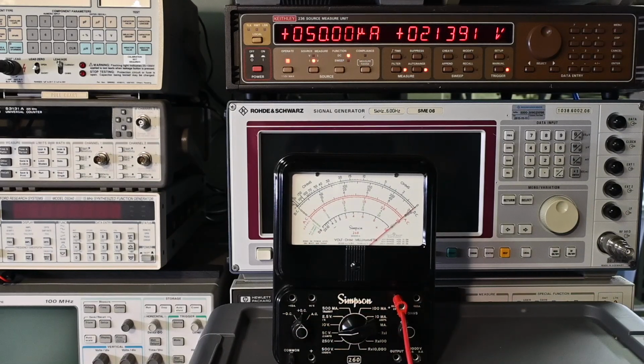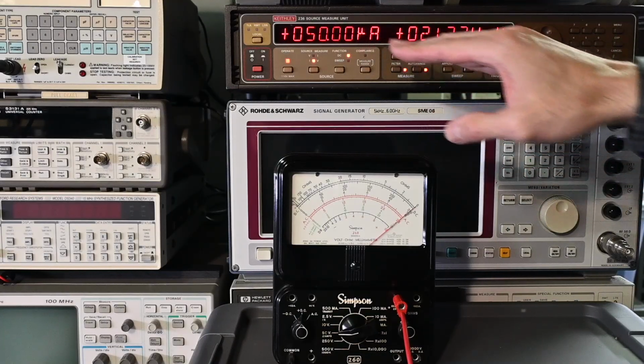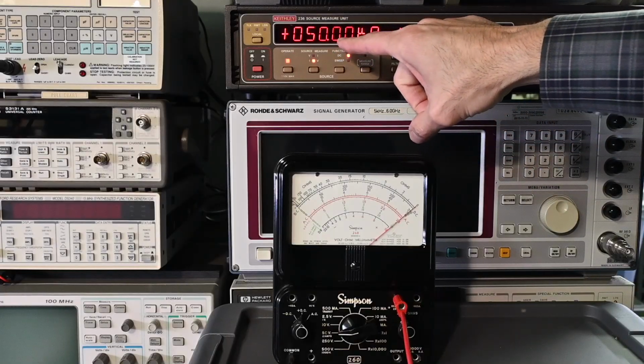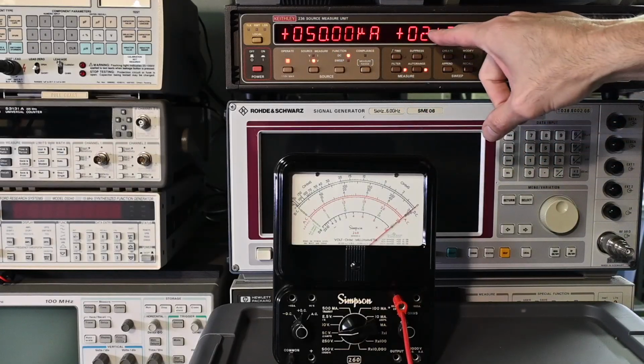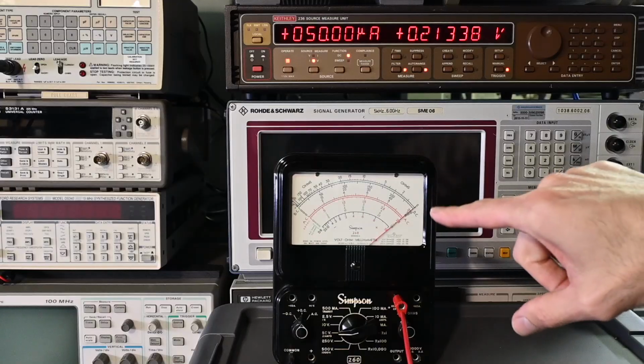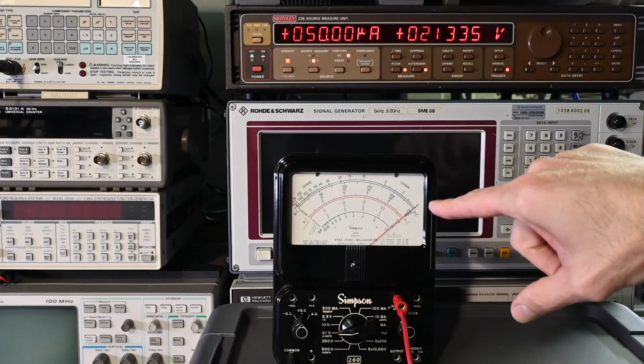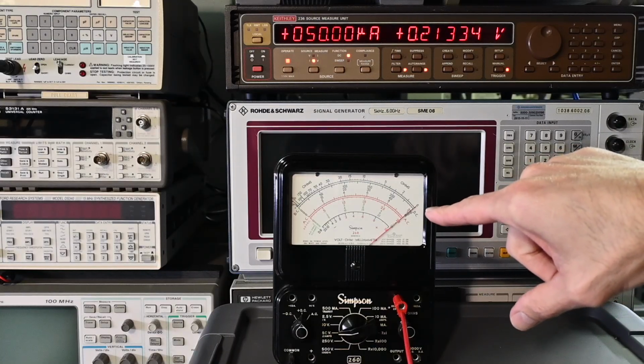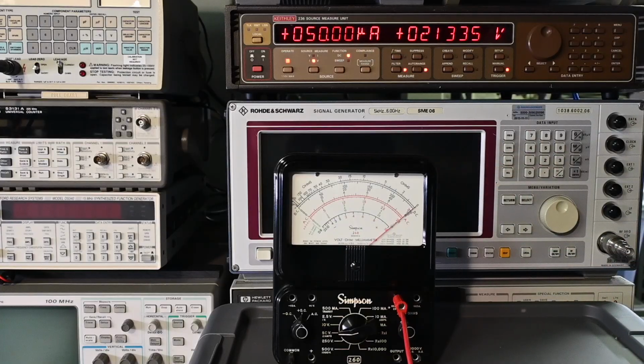All right, so I want to show you what not to do first when you're doing the second DC calibration, and that's to use a constant current source. So right now this is still in the 50 microamp constant current setting, and you can see the measured voltage. Now this is indicating right on the first tick mark on the right hand side, and you'd say, well, it looks calibrated at this point, but this is what you don't want to do, and here's why.